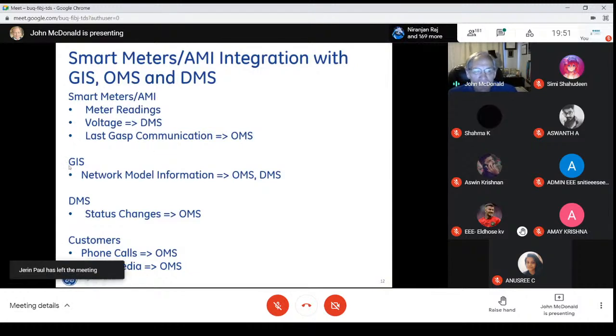The geographic information system is the reference system for the network model for the outage management system and the distribution management system. We take status changes from the distribution management system, and one example would be a distribution feeder breaker now trips. So that feeder is de-energized. We take that one piece of information and send it to the outage management system. It has the network model, so it knows now that feeder is de-energized, it knows all the customers that are connected to that feeder, and it knows now that all those customers have an outage.